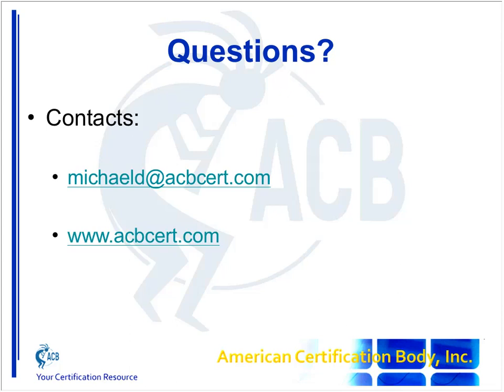So you've installed the module, tested safety and EMC, tested any missing radio emissions, for example, but some radio test cases you've decided to trust. Then you are fully responsible for that end product which contains a radio. So your end lab equipment user manual will contain the rated output power and frequency of your Bluetooth. Your name and address will be on the product and on the user manual. Your declaration of conformity will be to the RED, and you'll list the EMC and safety standards you used, and the radio performance standard you used or the module manufacturer used. Okay, hopefully that's quite clear.